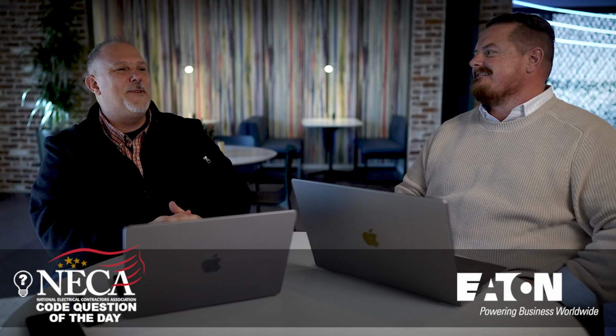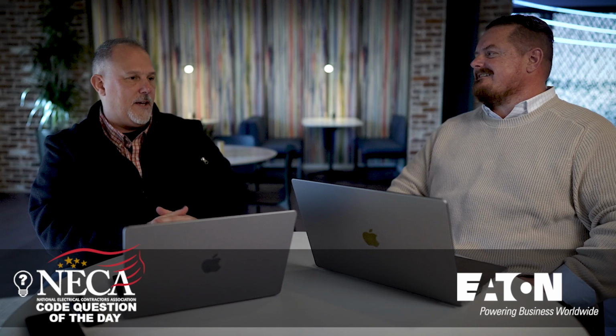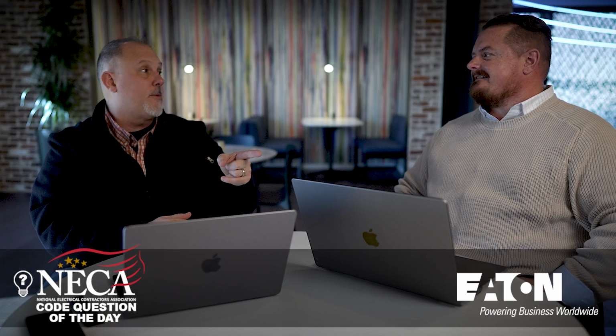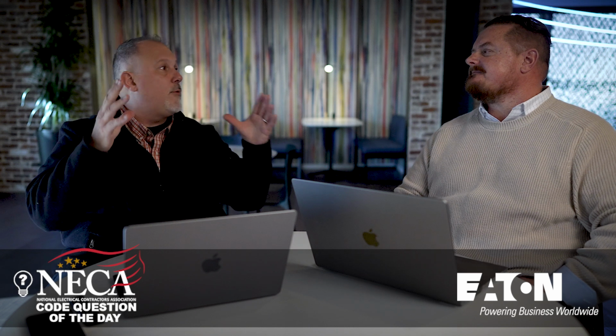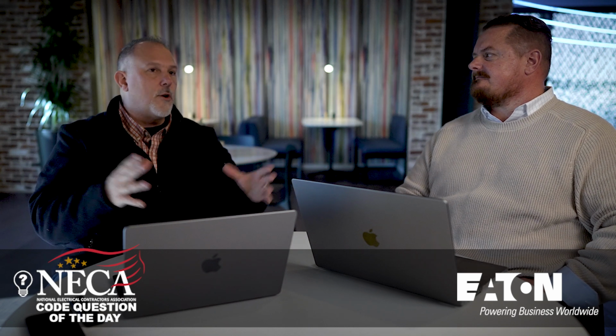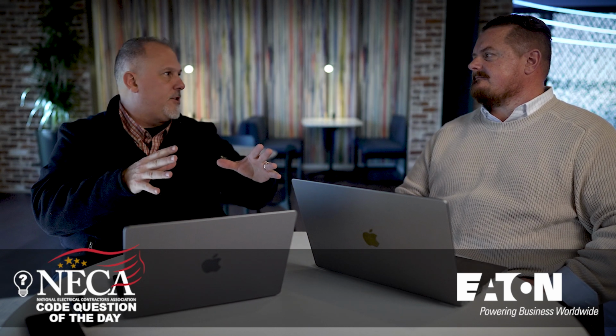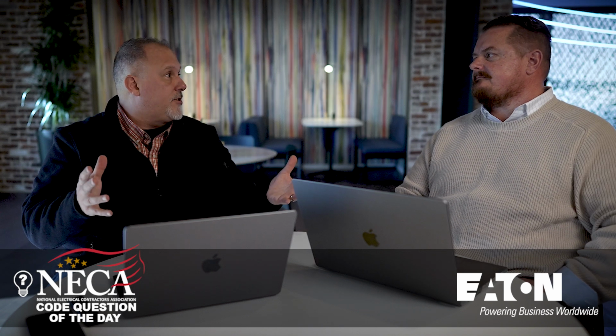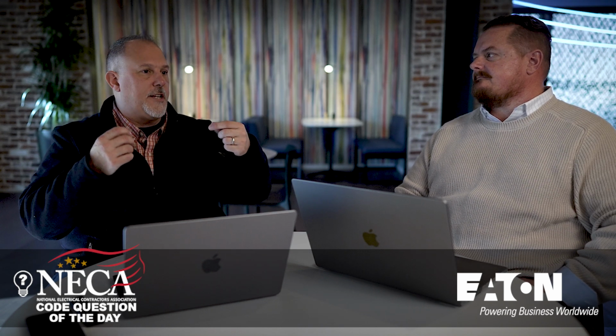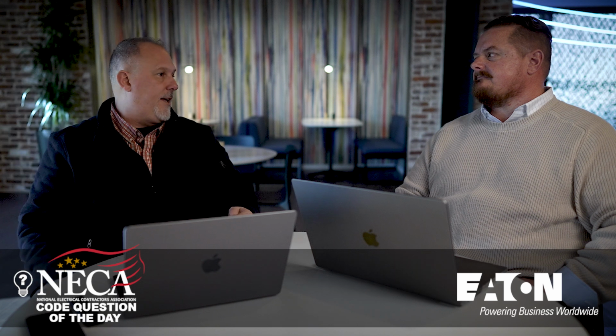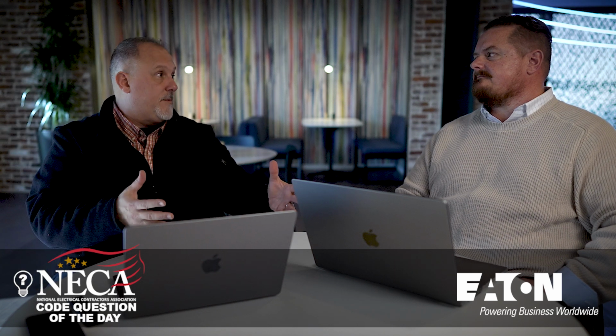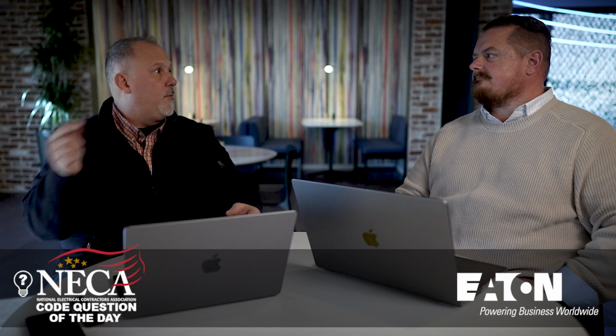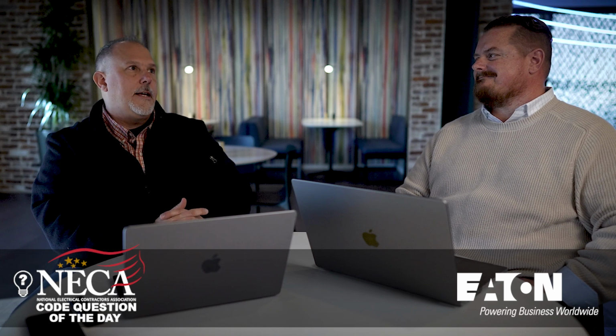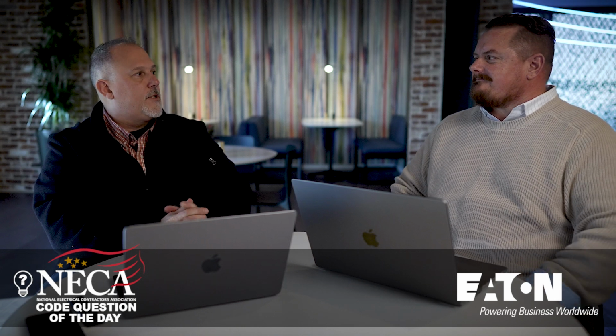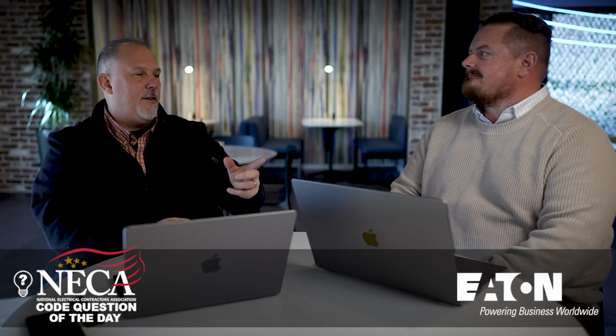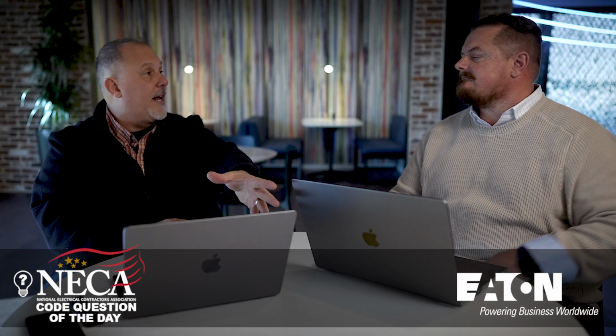I'll tell you what happened. I had an individual call me about an issue with a machinery. It wasn't an industrial control panel. It was an old piece of machinery. You weren't going to modify the control circuit for it because it was vintage, right? And it was one of these products that you see in a manufacturing facility where you just say, I got to live with this piece of machinery and hopefully it never breaks because you're making your own parts for it. So his issue was the fault current was way higher. So I had gone down the road of putting a fusible disconnect right in front of it.